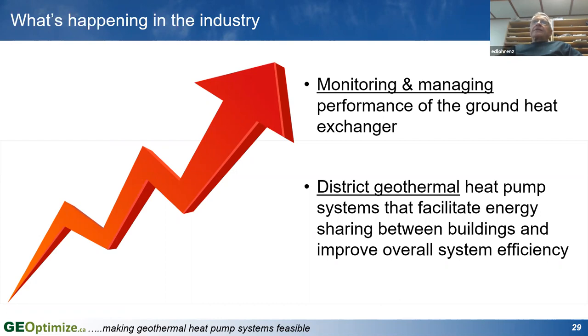And the second thing is energy sharing. For example, if you've got an office building adjacent to a school that's adjacent to an apartment building, or a bunch of single family homes, the energy load profiles of each of those different types of buildings, because the buildings are being used in different ways, are going to have their peak heating and cooling loads at different times of day. An office building is going to have a peak cooling load, typically at 3 or 4 or 5 in the afternoon, when the sun is beating in on the building and there's the most people in the building, lights are all on, computers are all on. That's when the cooling load is going to reach its peak.